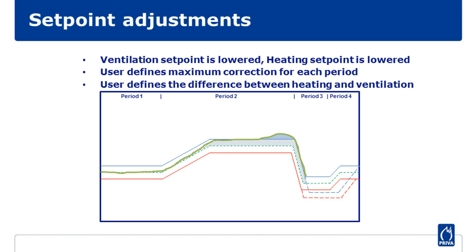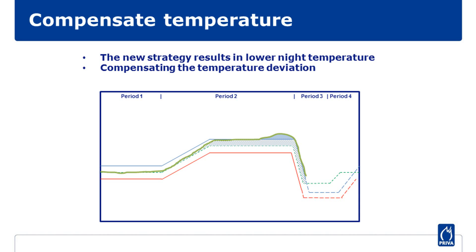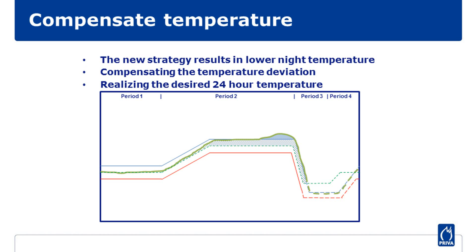As a user, you can set which period you want to apply a correction, and how many degrees relative to the leading control you want to correct up or down. The difference between ventilation and heating — the dead zone — should be minimal. The green hatched area you see is the rate of temperature correction. Notice that the modified strategy results in a lower temperature in the night period. This is to correct the temperature deviation of the day period. With the automatic adjustment of the ventilation and heating strategy, the temperature deviation of the day is now corrected in the night period. This will result in a lower glasshouse temperature as shown in this example.